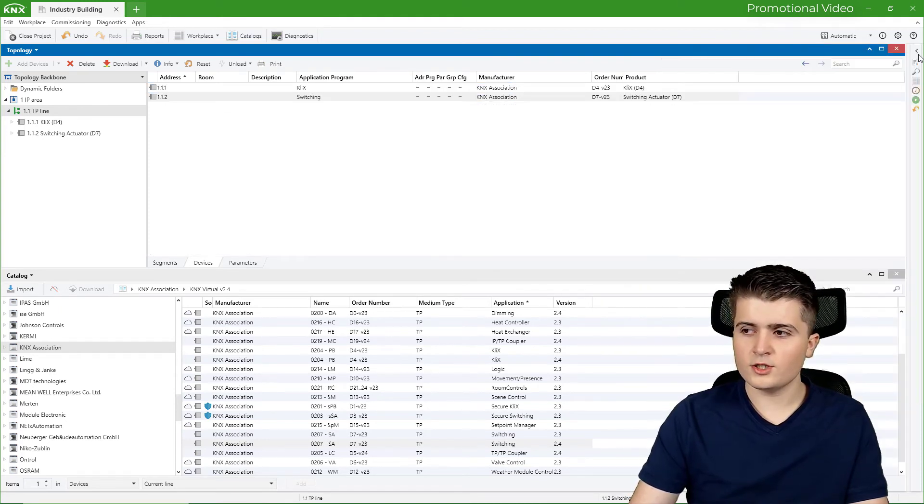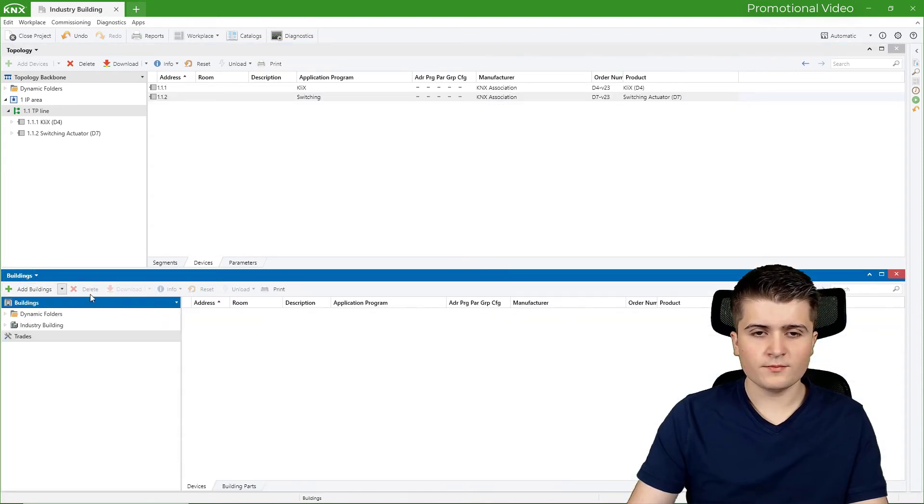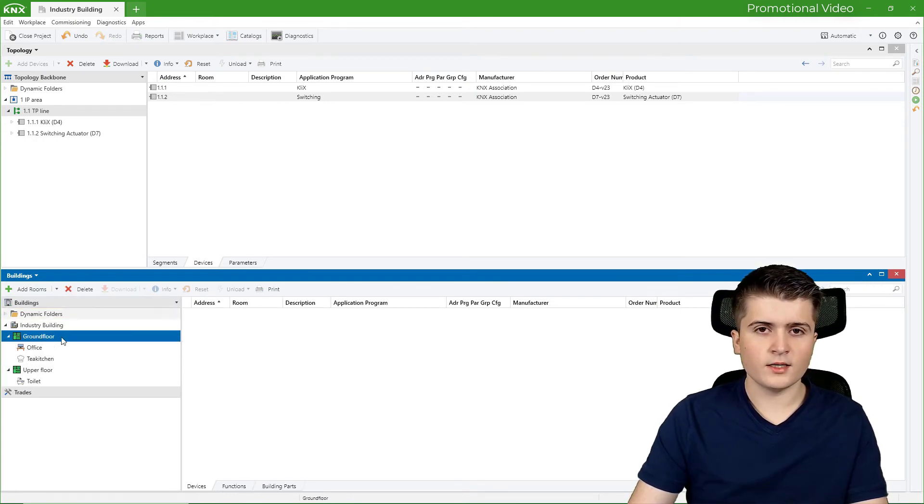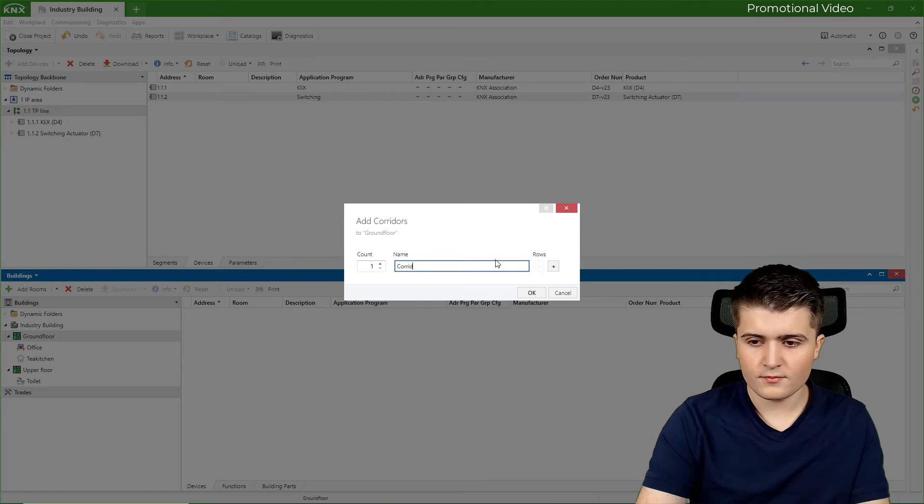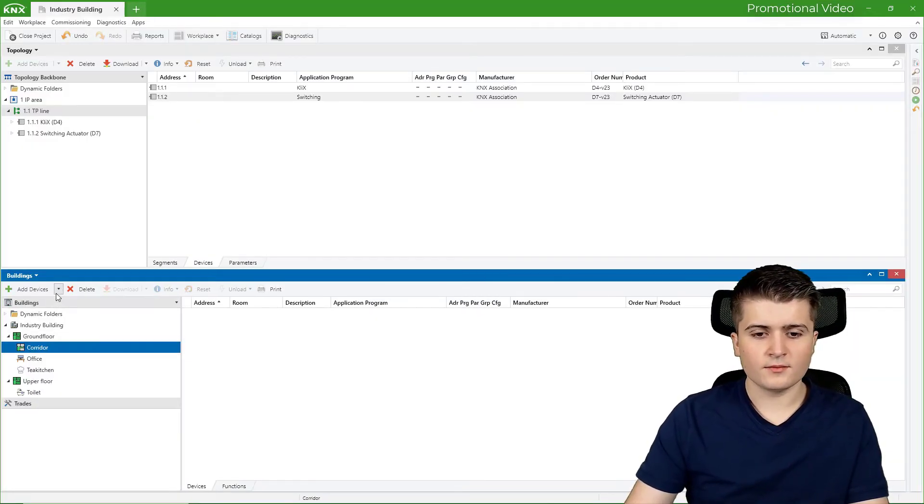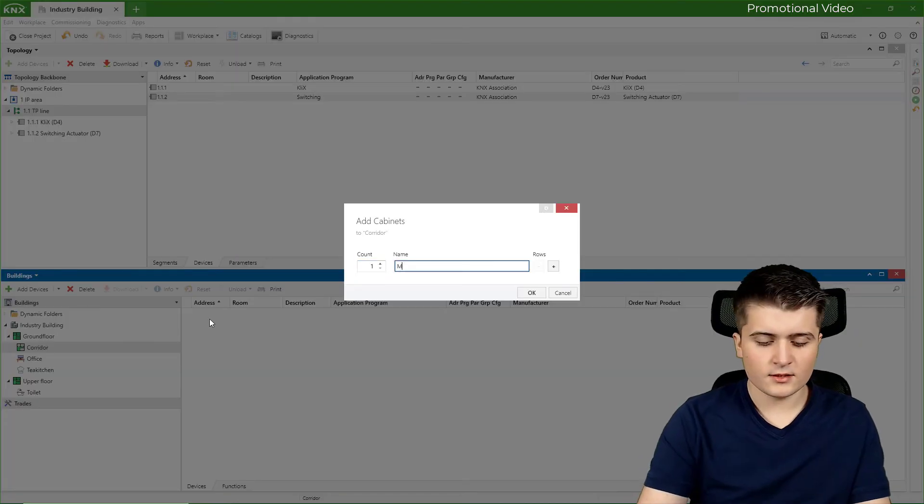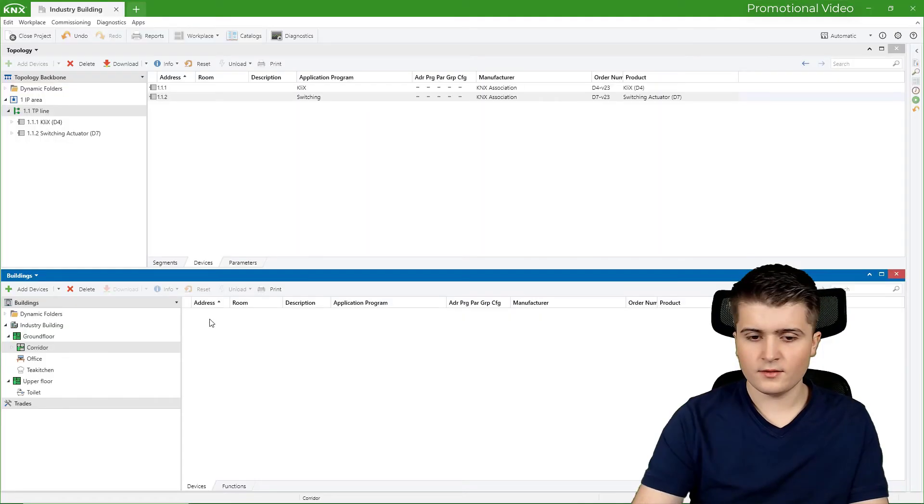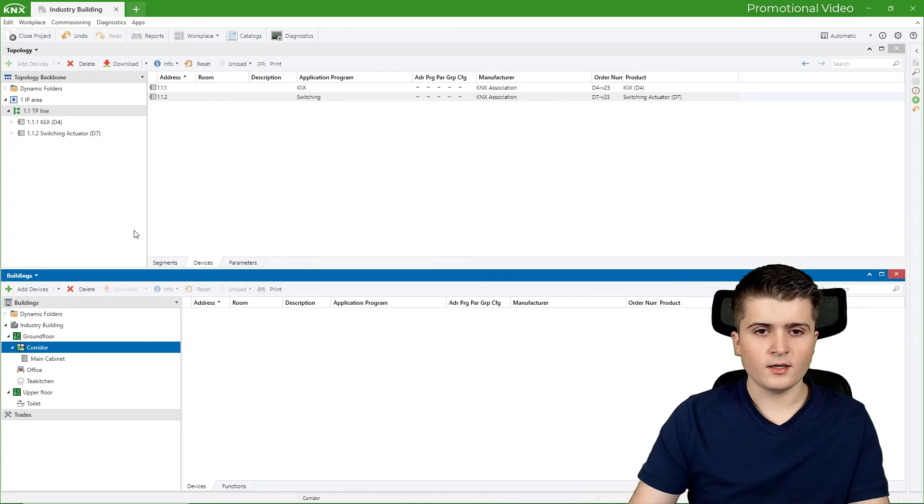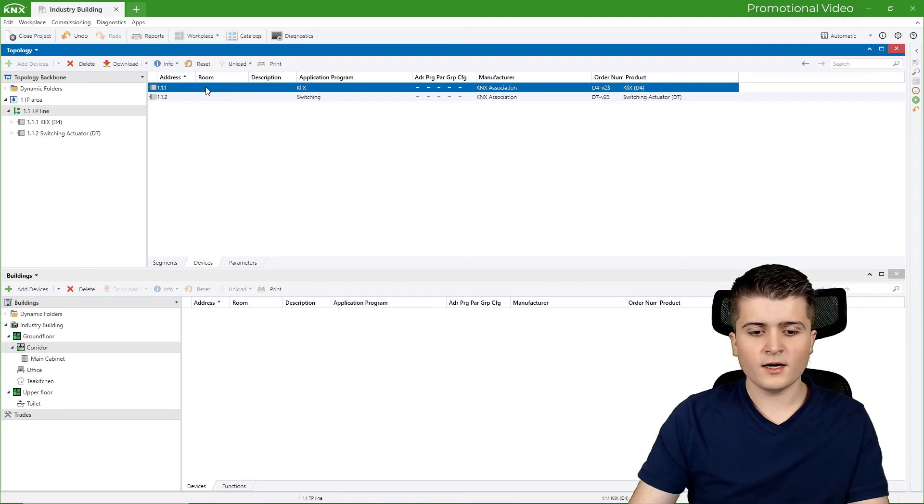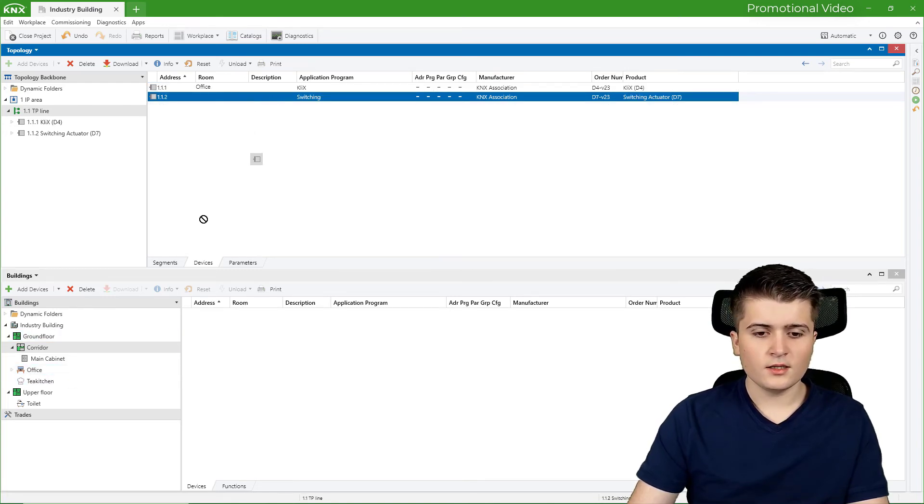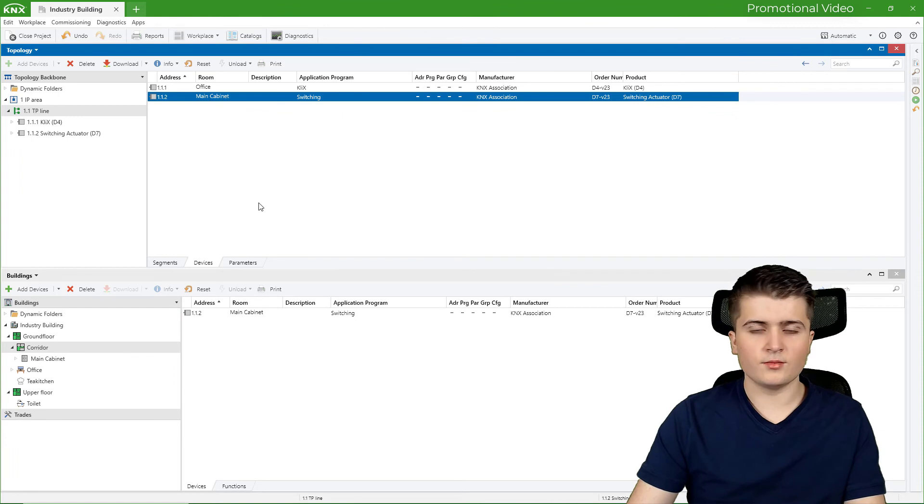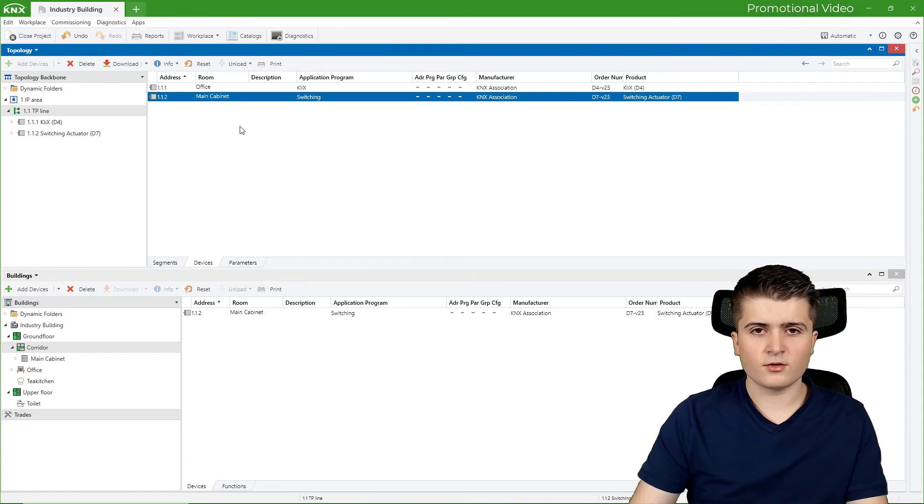And this is what I want to change now. Therefore I open up here the buildings page. So I changed catalogs to buildings. And then I also want to add a corridor to my ground floor. Therefore here on this button and then directly here on corridor. And in this corridor I want to have my main cabinet. Therefore again here on the arrow, cabinet and main cabinet. And inside of this main cabinet I then want to insert my switching actuator to it. So therefore I will go back here to the topology. And now I simply drag and drop the devices into their associated room. So for example the push button sensor into the office. And the switching actuator into the main cabinet. And quickly go back and into the main cabinet. Now you can see that both devices are associated to their corresponding room.